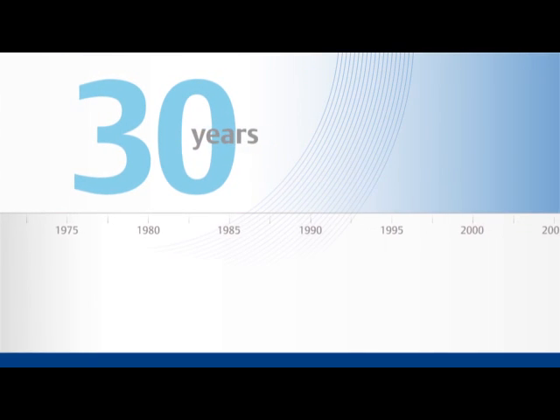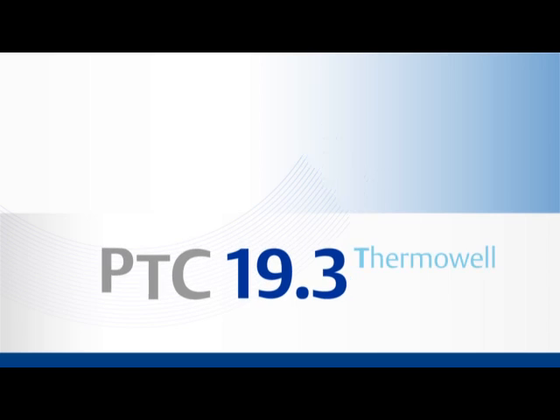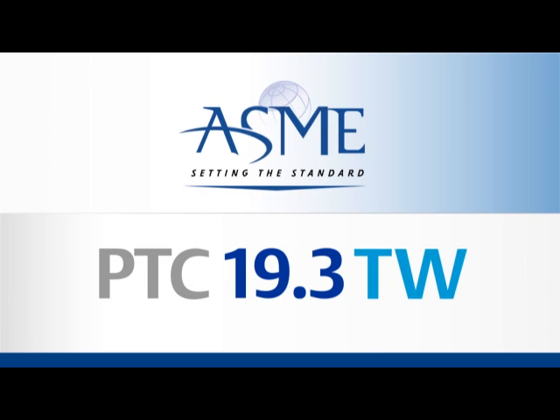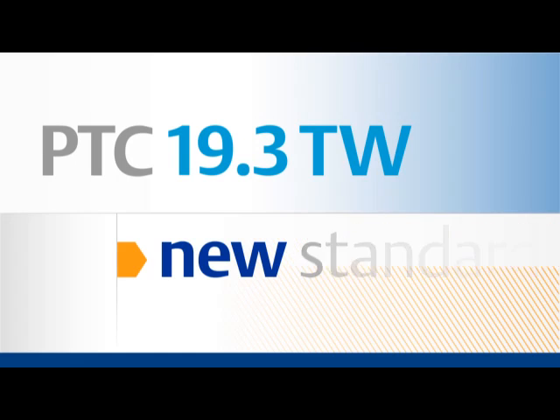For over 30 years, Thermowell calculations have been guided by Performance Test Code 19.3. Recently, the American Society of Mechanical Engineers, or ASME, updated the code. The new standard, called PTC 19.3TW, is the result of decades of work.